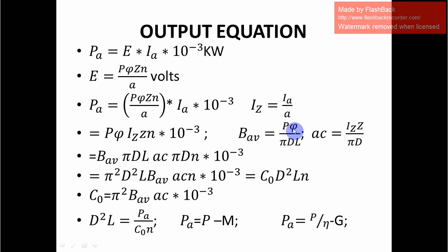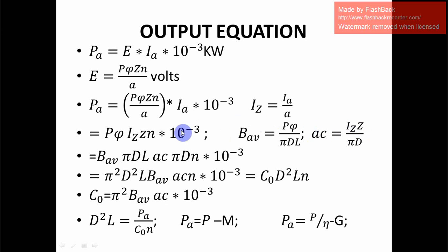From specific electric and magnetic loading: the average magnetic flux density B_av equals the total magnetic loading P·φ divided by π·D·L. Similarly, the specific electric loading AC equals total electric loading I_Z·Z divided by π·D. From these two relationships we can find P·φ as well as I_Z·Z, which we substitute into the previous equation.